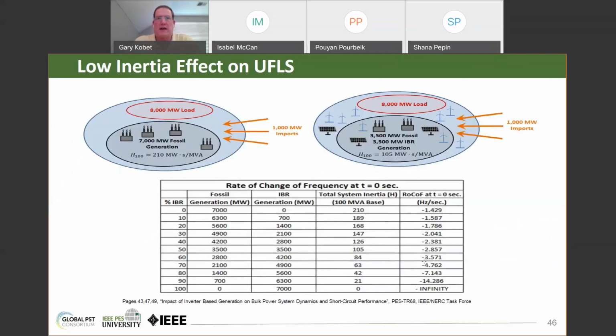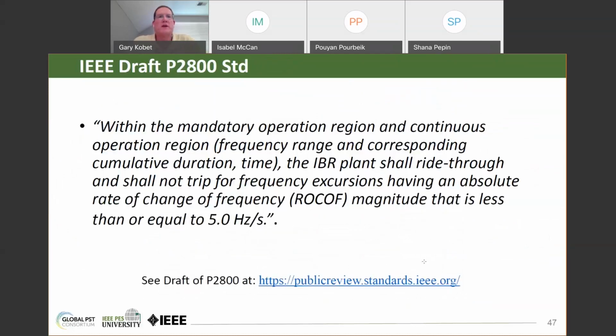The next slide shows a part of the P2800 standard that requires that the IBR plant shall ride through and not trip for frequency excursions with a rate of change of frequency less than or equal to 5 hertz per second. So that's something that the P2800 standard calls for.